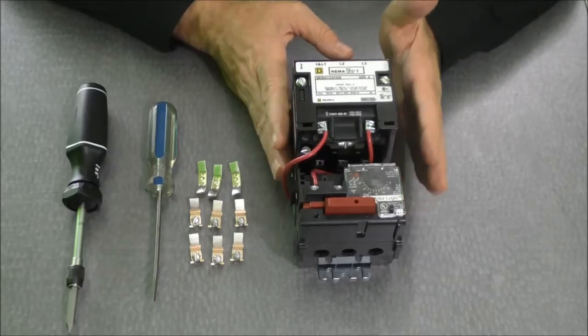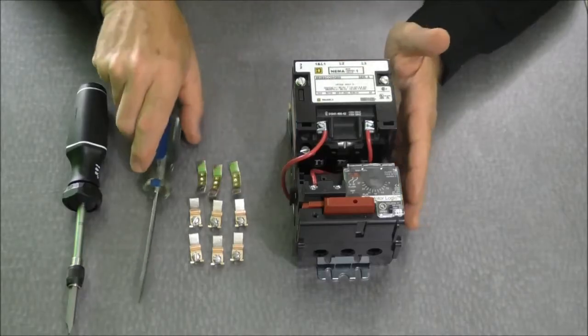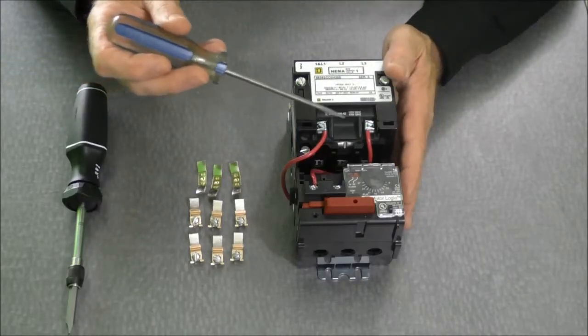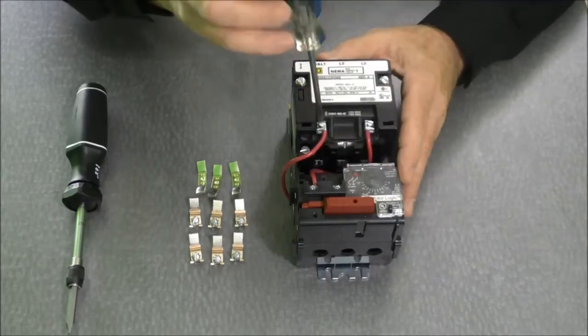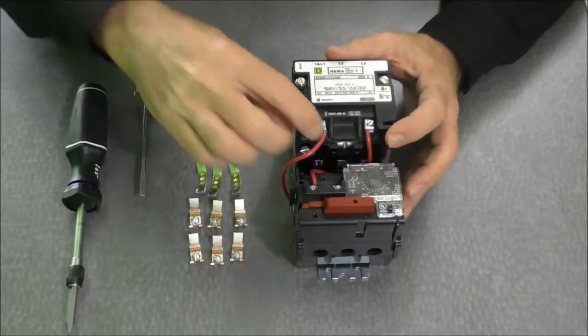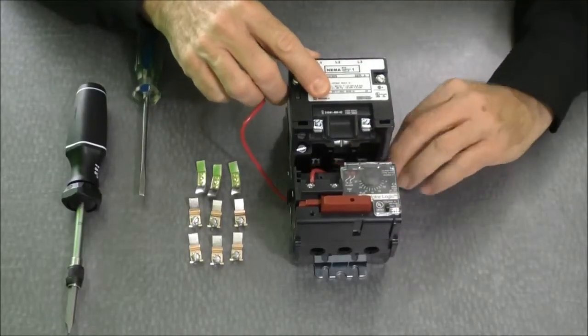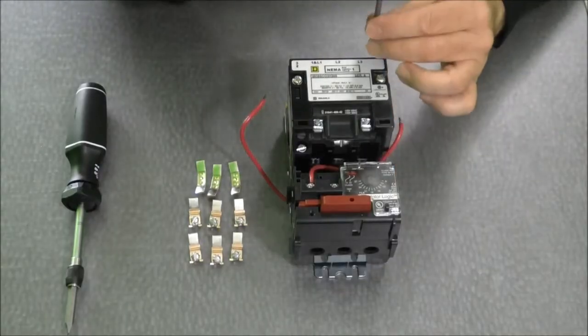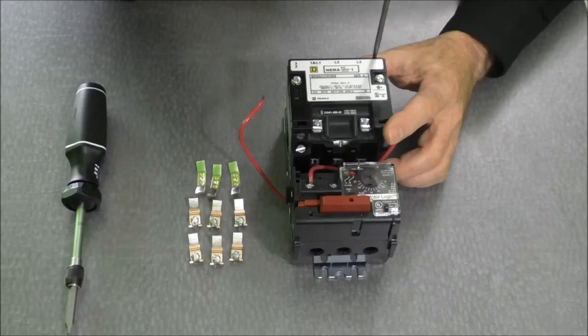So to begin with, to get access to the contacts, the easiest thing to do is remove the wires to the terminals on the coil. So I'm going to remove both the A1 and the A2 wires. I'm going to pull those to the side so that I can loosen the screws to the contact itself.